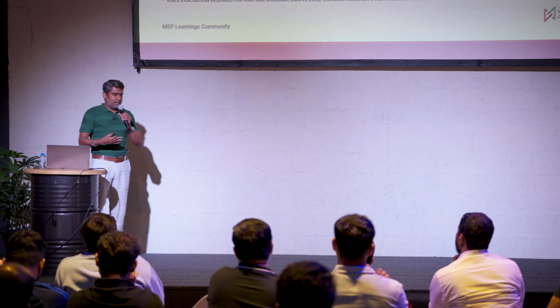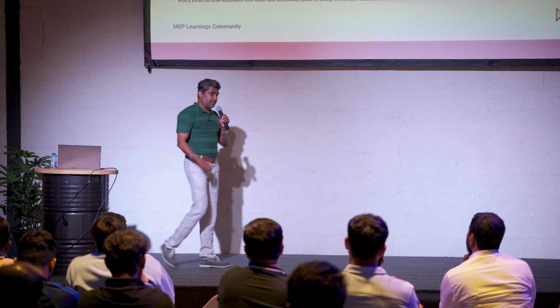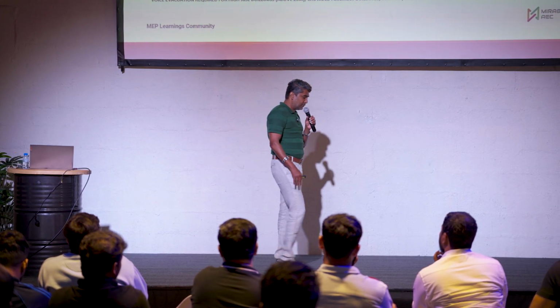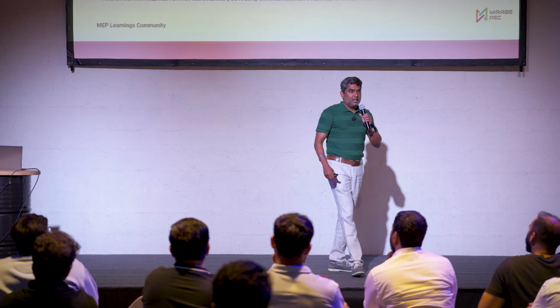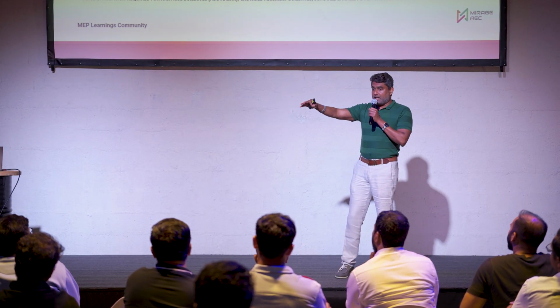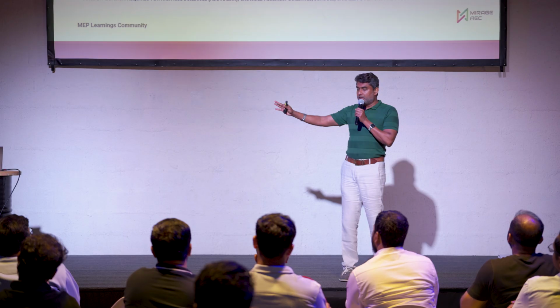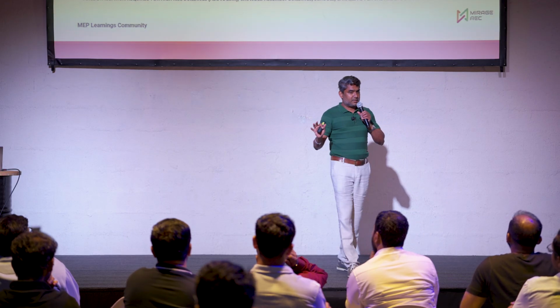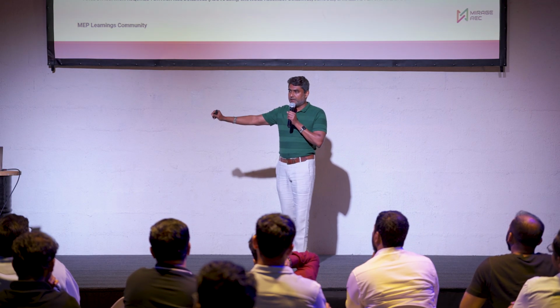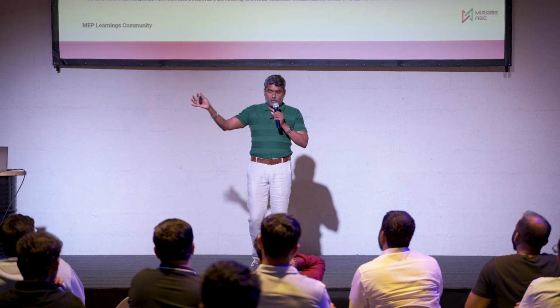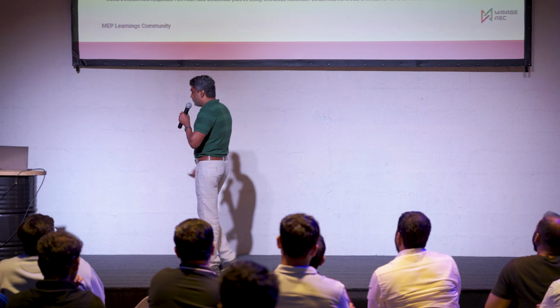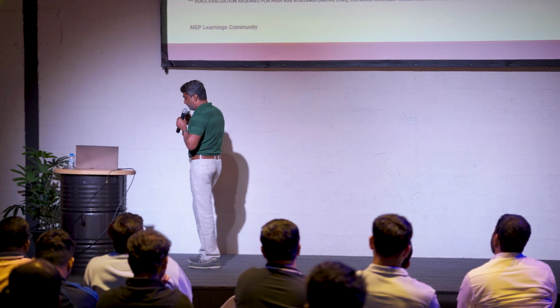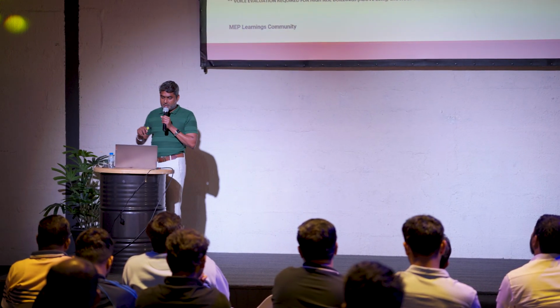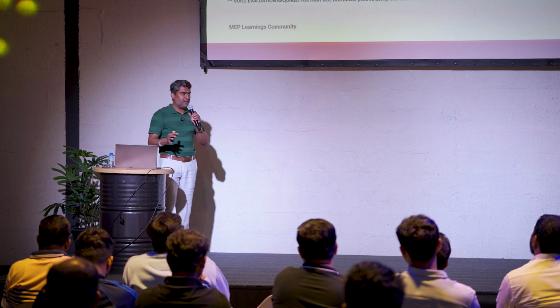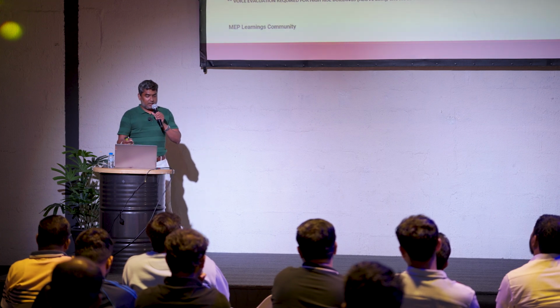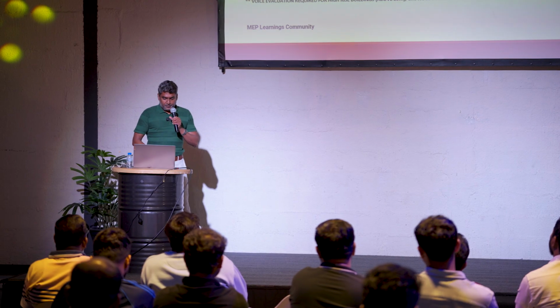Since I started with BS, my thought is search distance is 30 meters, while NFPA allows up to 45 meters. Search distance is the distance to reach any manual call point around me - it cannot be a straight line, sometimes it has to go around the core and through alleys. If the search distance exceeds the 45 meter criteria, you'll have to add additional manual call points in between.